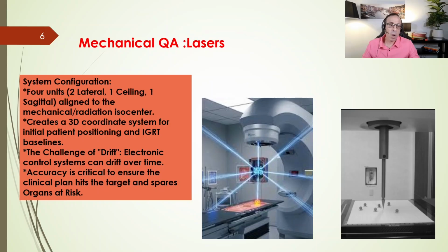If lasers are your primary setup tool in patient setup, any drift directly translates into positioning error. To hit the target and spare critical structures, we must keep these errors within a 1 to 2 millimeter window. If we are using IGRT for patient setup, and we know that the IGRT system provides the final corrections, we still need the lasers to be accurate. A stable laser baseline ensures that the shifts we see on our screens are meaningful, and the patient is starting in a consistent position every day.